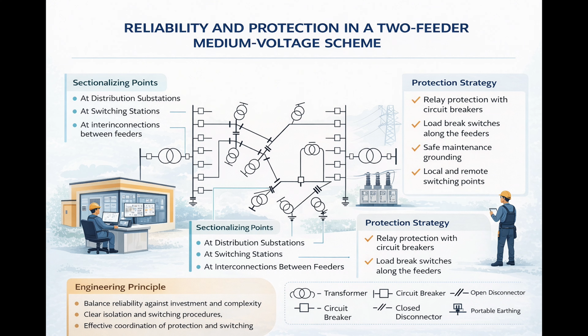From a system design perspective, you must ensure safe isolation procedures, clear switching sequence during faults, reliable grounding during maintenance, and coordination between relay protection and switching devices. For example, if a feeder breaker trips due to overcurrent, operators must verify the faulty location before reclosing. If maintenance is required on a feeder section, it must be disconnected, isolated from all possible supply sources, and grounded securely. Reliability does not depend only on the network topology, it also depends on the protection performance and switching device reliability.